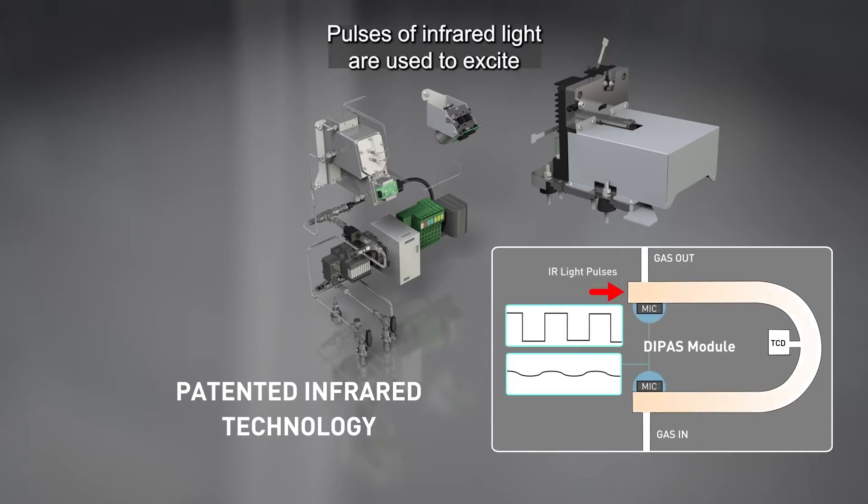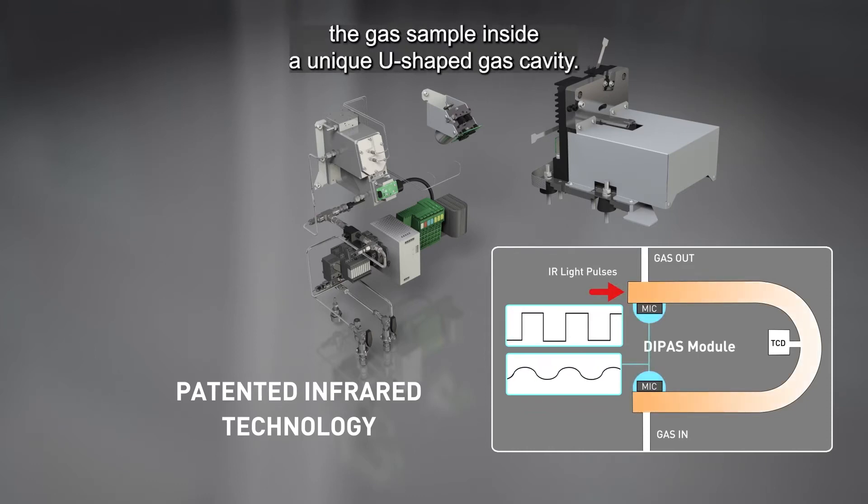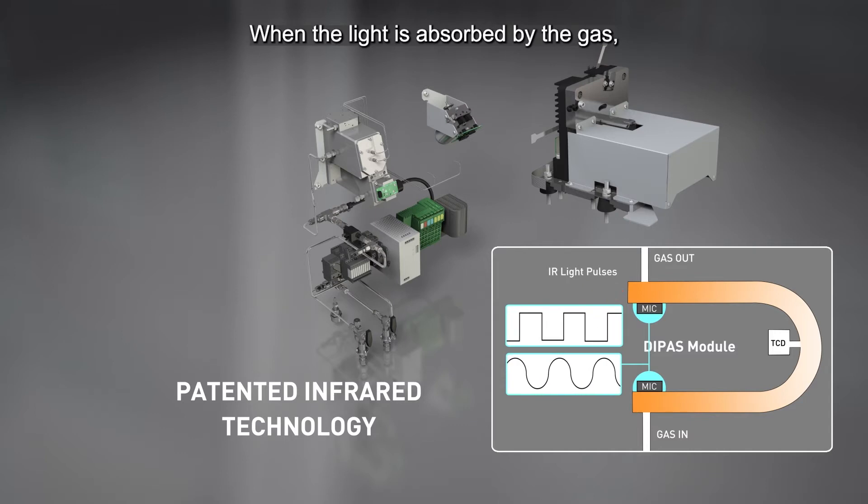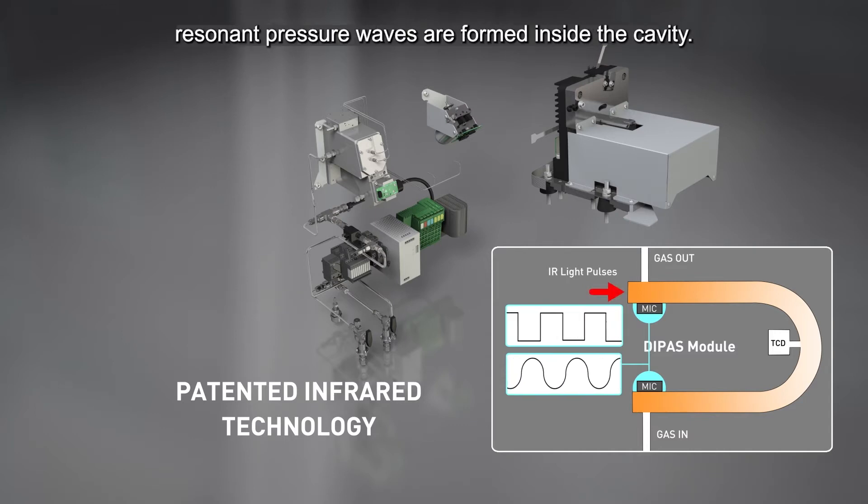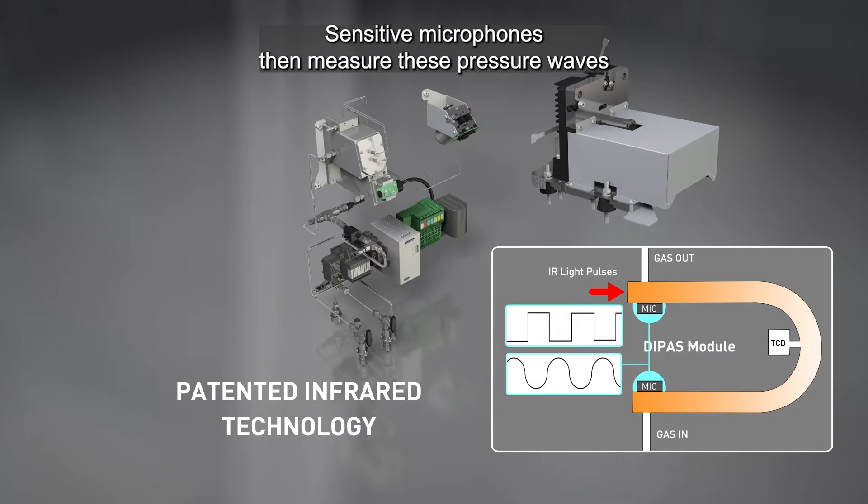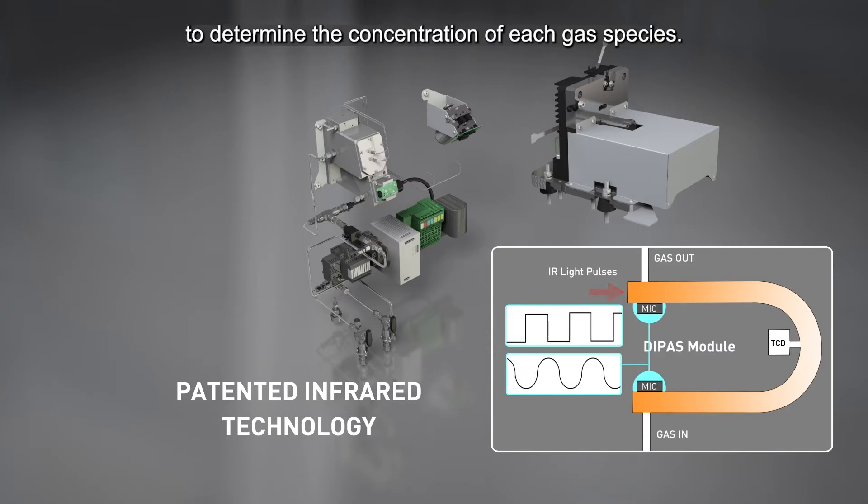Pulses of infrared light are used to excite the gas sample inside a unique U-shaped gas cavity. When the light is absorbed by the gas, resonant pressure waves are formed inside the cavity. Sensitive microphones then measure these pressure waves to determine the concentration of each gas species.